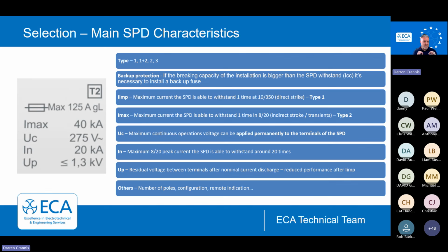They give you very, very small protection. That's what the Up stands for, 1.3 kV. So it will still work. It's basically like the car limp home. It's just giving a little bit of protection. The rest of the overvoltage is just going to keep going past it. And there may be some other writing from the manufacturer on these as well, maybe some normally open, normally closed contacts or some other additional information that may be useful. But it's important that when you pick these up from the wholesalers, you understand what it can do, what its capacity is.